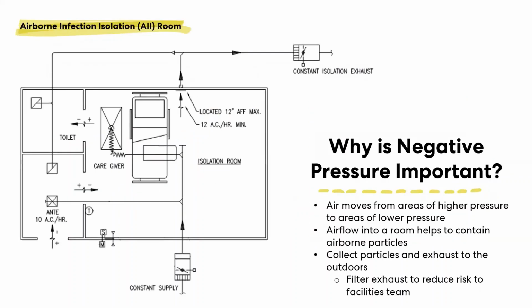So negative pressure is important because airflow tends to move from areas of higher pressure to lower pressure, and it moves the particles along with it. Typically, as Jerry mentioned, the hospital has about 40 isolation rooms that are standard and set up for this operation, or for treating patients with infectious disease. The isolation rooms are negative to the surrounding spaces, and therefore airflow moves from the surrounding spaces into those spaces, keeping the virus particles contained to the space. The diagram on the left shows a typical isolation arrangement where we supply air above the caregiver. That air moves across the patient bed into a low wall exhaust outlet.